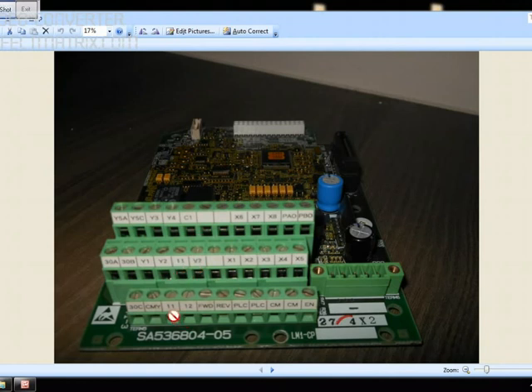So in this you can see C1. This is the analog input current. Current you can give here. This is the terminal for which the range will be 4 to 20 milliamps. Whereas V2 is the voltage. Voltage will be from minus 10 to plus 10, for which the common terminal will be 11 here. And 11, there are 2 terminals for that. And 12 is for the voltage again.